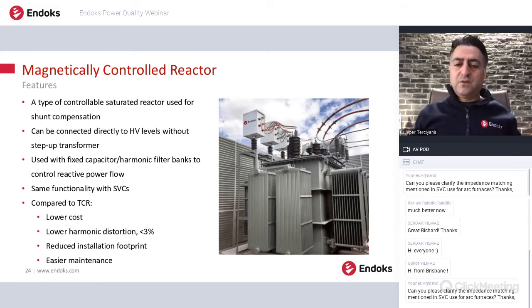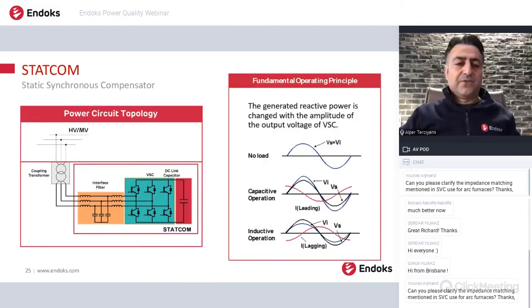So, what is the main disadvantage then? We are talking only advantage. The main disadvantage here is that the response time is a bit long compared to SVC. So the MCR cannot be used for flicker reduction, because for flicker reduction, we need very fast response. So this MCR cannot be used for flicker correction or flicker elimination, and also cannot be used for very, very fast varying loads like arc furnaces. But still, the response time is around 1 second. So any load having 1 second variation in reactive power, these MCRs can be used as a very low cost and optimum solution. And we are using a lot in our country.